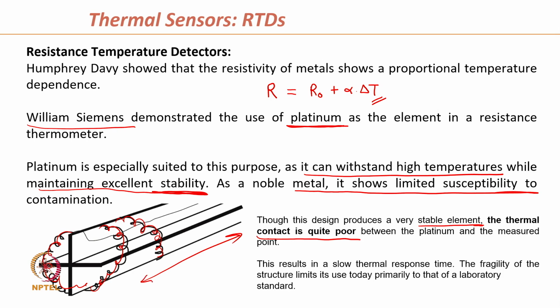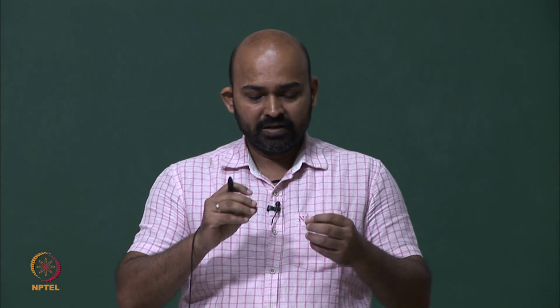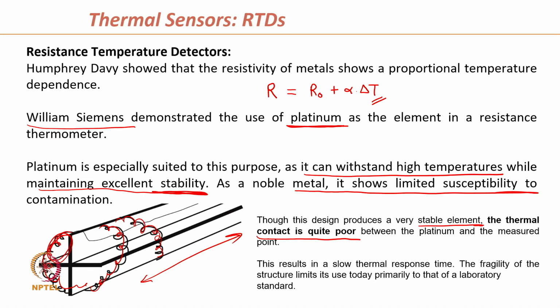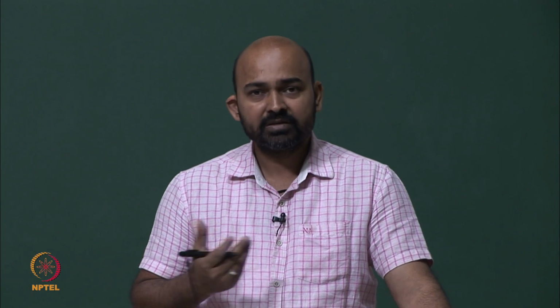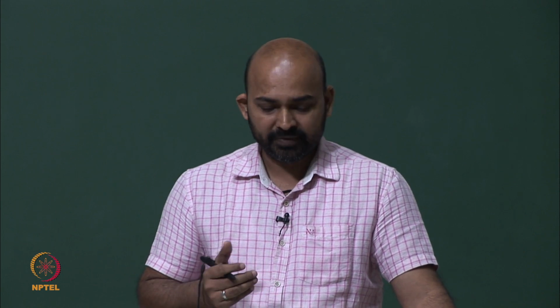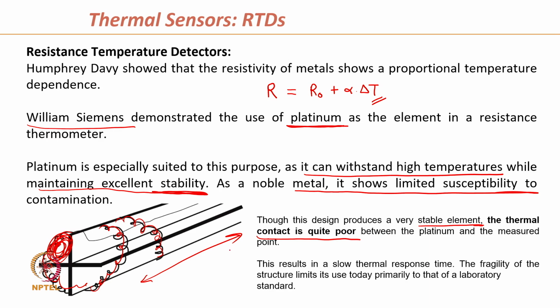So, when we make this kind of sensor, how do we have a proper contact of this assembly with a heated body, let us say, which is circular in nature? A very small portion of this assembly, let us say this portion only, gets in contact with the heated body. So, it limits the thermal contact area, which gives us different kinds of errors in the measurement. So, this is the limitation of this kind of design, which results in a slow thermal response time.